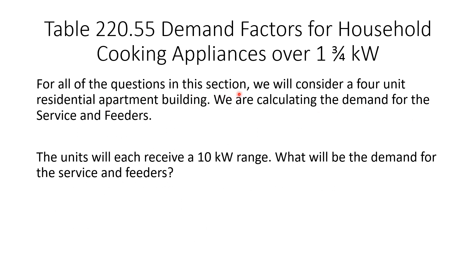For all the questions in this section, we're working on a four-unit residential apartment building. We're calculating the demand for the service and the feeders. The reason we make this adjustment is because this is residential — not everyone in the building will be using their cooking equipment at the same time, so we can reduce the size of the feeders and service accordingly.